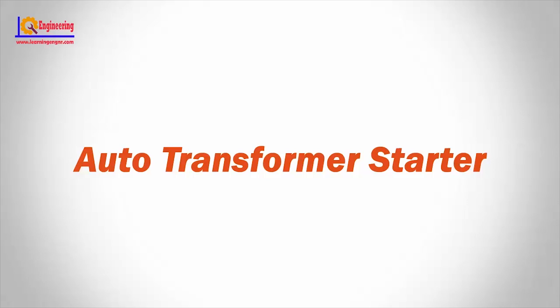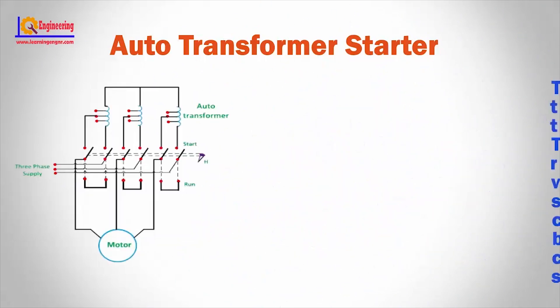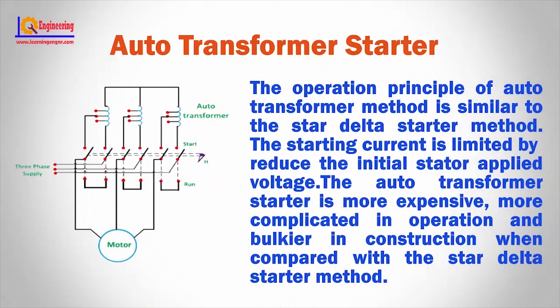Auto transformer starter. An auto transformer starter is suitable for both star and delta connected motors. In this method, the starting current is limited by using a three-phase auto transformer to reduce the initial stator applied voltage. The operation principle of the auto transformer method is similar to the star delta starter method. The auto transformer starter is more expensive, more complicated in operation, and bulkier in construction when compared with the star delta starter method.